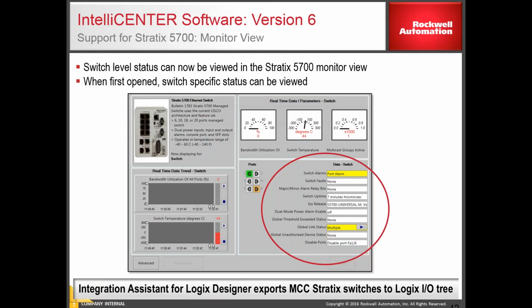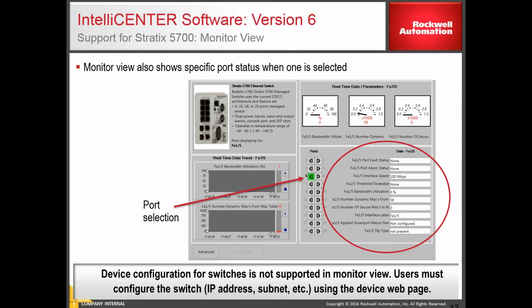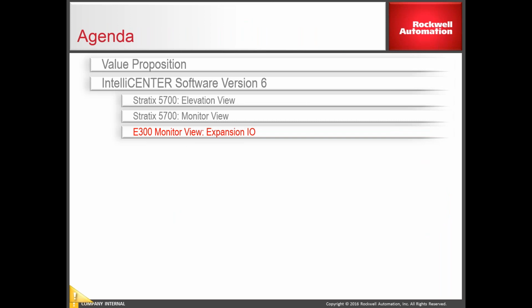And there's also a monitor view now for the Stratix switch. Now you can't configure the switch through the monitor view, but you can monitor status information within the Stratix 5700 switch. You can also monitor the port configuration. So you can do some troubleshooting. If you've got some communication issues, you can do some troubleshooting using this monitor view in the IntelliCENTER software. And again, you can't configure it, but you can definitely monitor it. If you need to configure it, you're going to have to use the web page, or with Studio 5000, you can go in and set up the Stratix switch that way as well. Any questions about that?